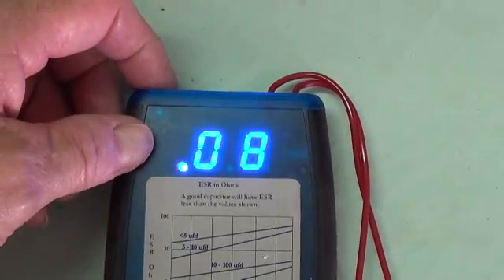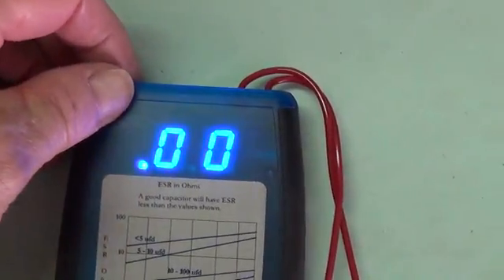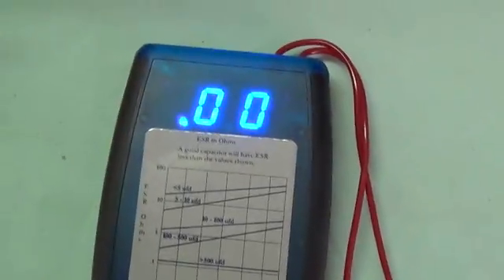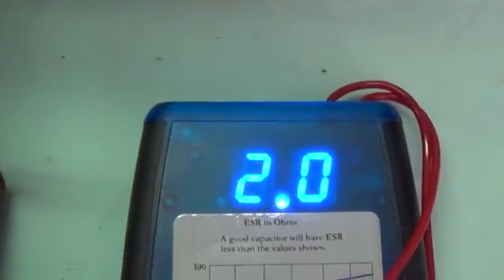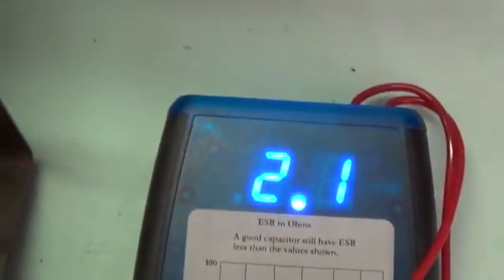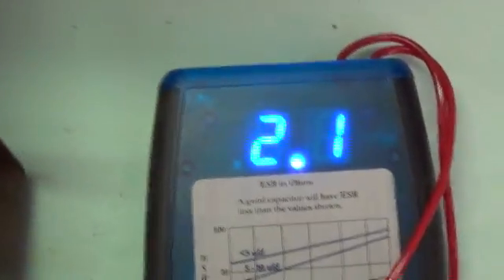Using the meter is extremely simple. You can hook the two probes together. You push this button once, and you'll get the reading of your resistance within the wires and probes. Push it again, and it zeroes. Then we're going to separate our probes and use them on the capacitors. The bottom terminal, 2.0. It functions as well as the brand new capacitors. The next terminal, 2.1. The third terminal, it's hard to do this with one hand, 2.1.